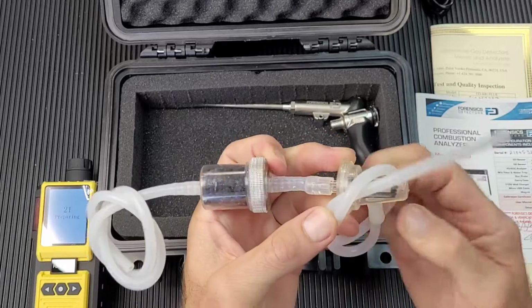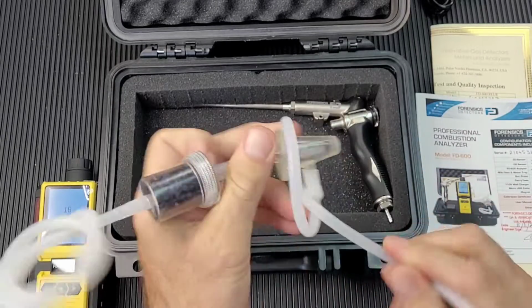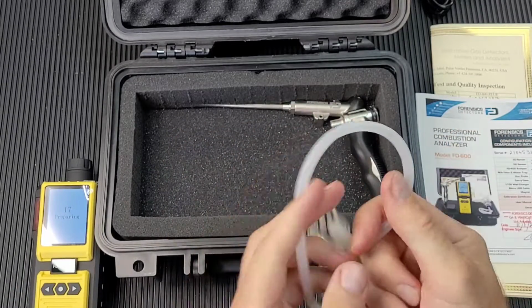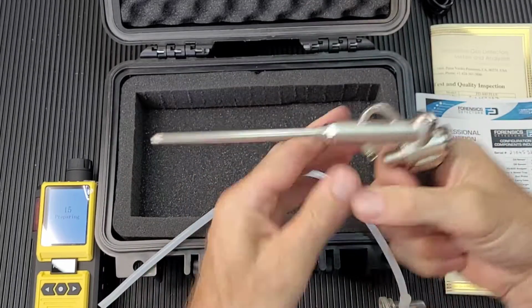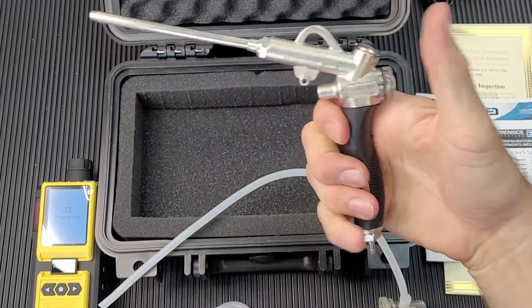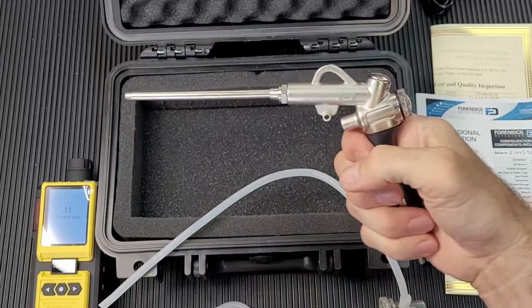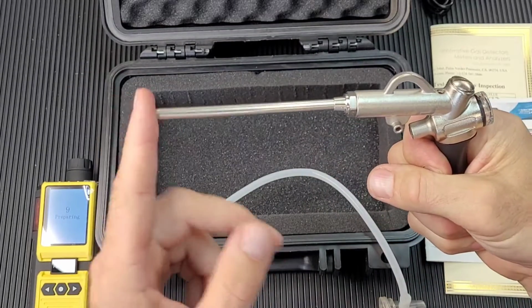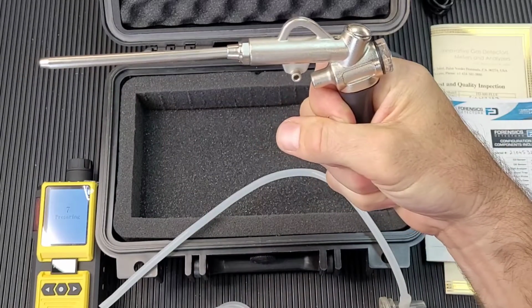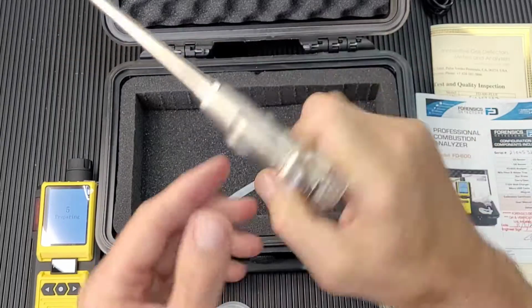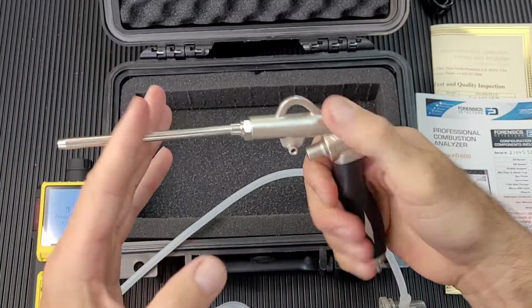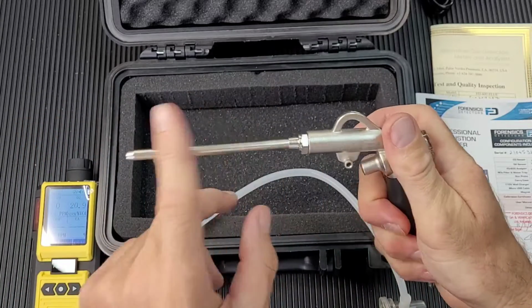Now, we have our combustion line kit, very important. Let's unwind this guy. And we have our pistol grip probe. This is Dr. Coz's. He loves this probe. Look at this. You pop it in, you drill your hole. Again, bang, you put it in your flue. And make sure, guys, anytime you're messing around with the flue, make sure you're not going to burn yourself. Probes are always stainless steel or metal. Make sure you're using a glove.